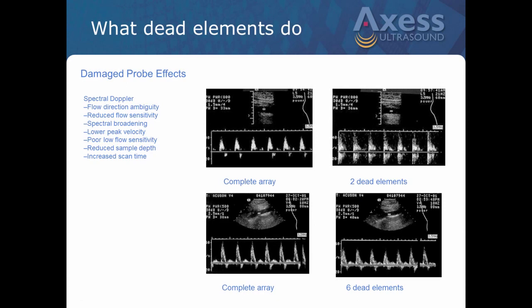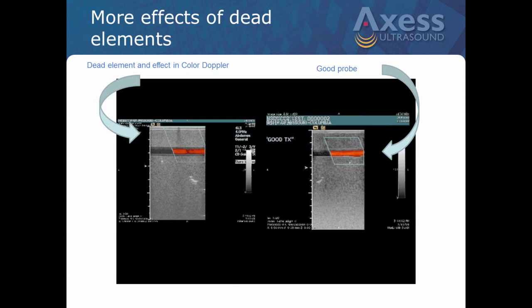Another question, from Logan: what is the difference between a weak and a dead element? If elements are binary, how can they be weak? That's a great question. In many cases, an element is not necessarily weak -- that typically leads me to look at the wiring to that element, to see whether it's making good contact. You can really get into it and look at the system side, to see if there's a channel out in the system that isn't providing the transmit/receive pulse properly to the probe. So that's typically where a weak element comes from. Ultimately, an element is either going to work or not, and either go bad or stay good.